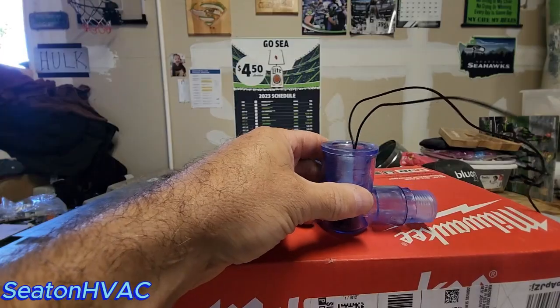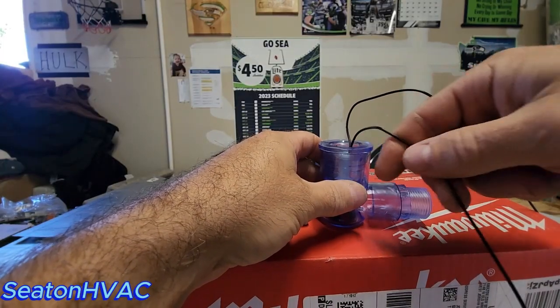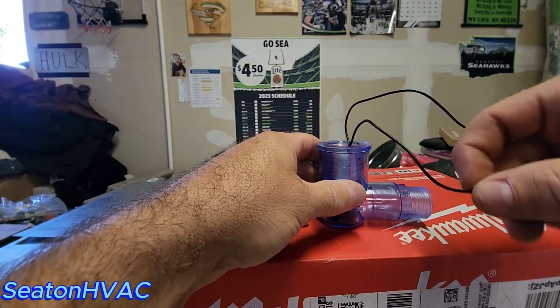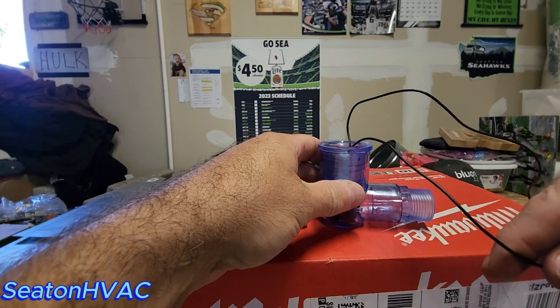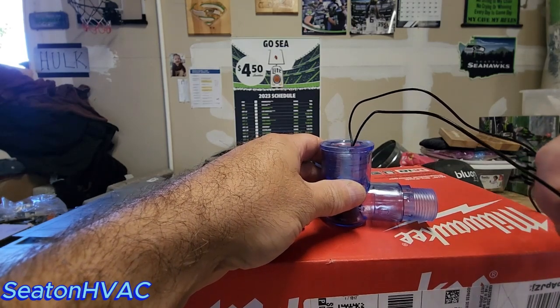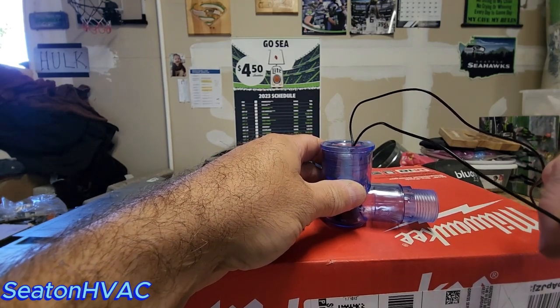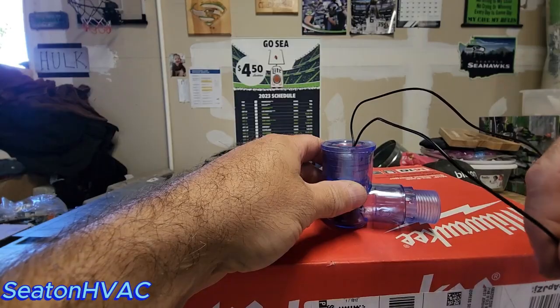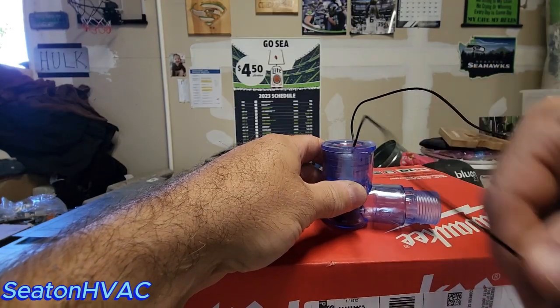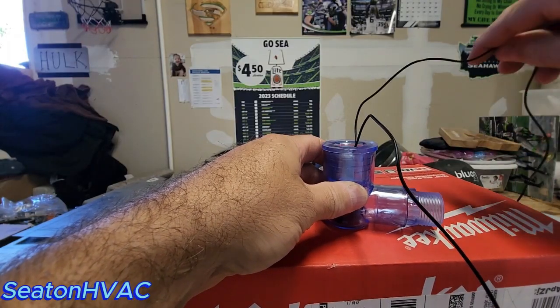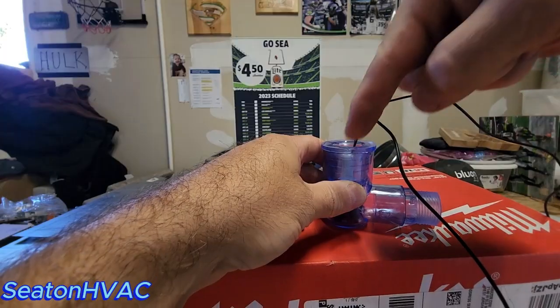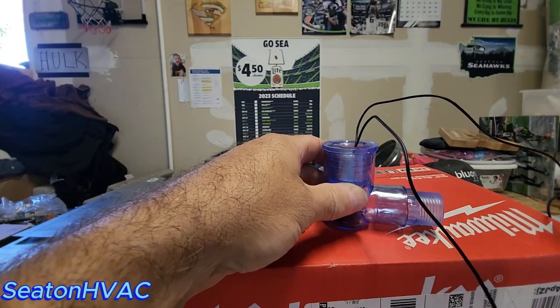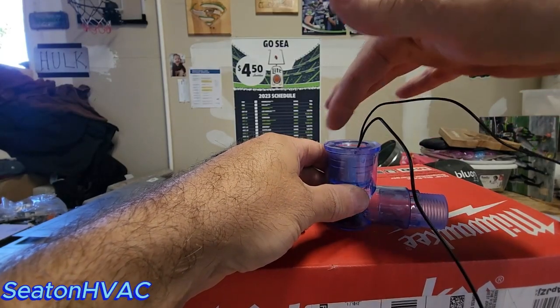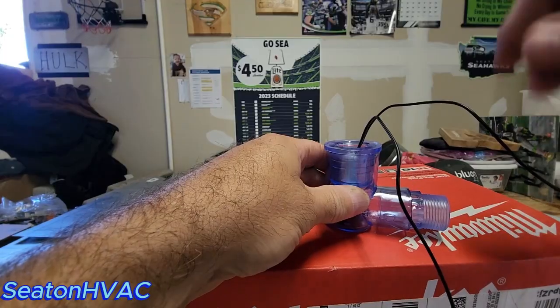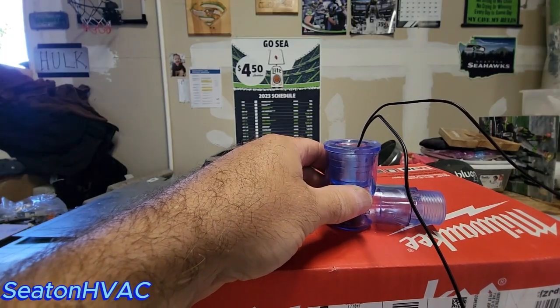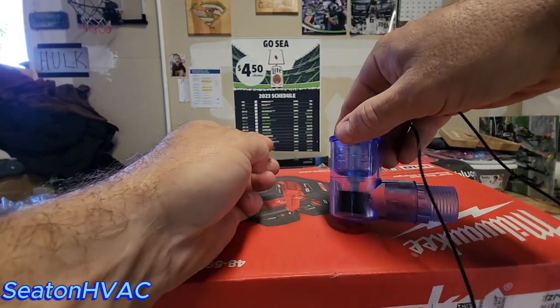So you're going to break, on a straight AC system, your Y wire inside of your air handling cabinet, okay? Don't land it to your low voltage terminal board. You're going to break it here. You're going to break it to one side, and then you're going to tie your other side to the terminal board. That way, your 24 volts is going to flow through your float and out. If that float pops up, it breaks it, doesn't energize your terminal board, it's not going to flood the customer's house. Simple. All floats are built the same.